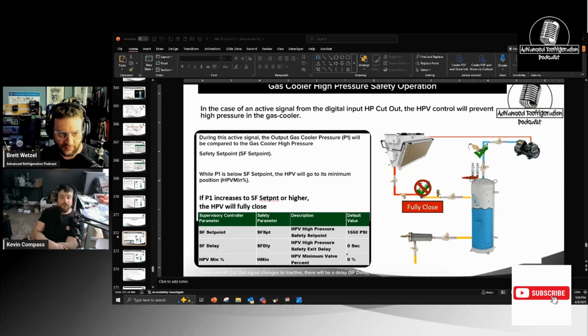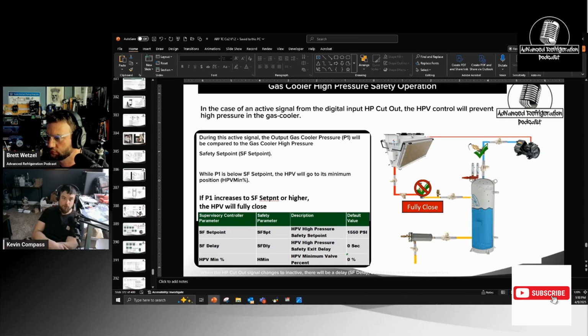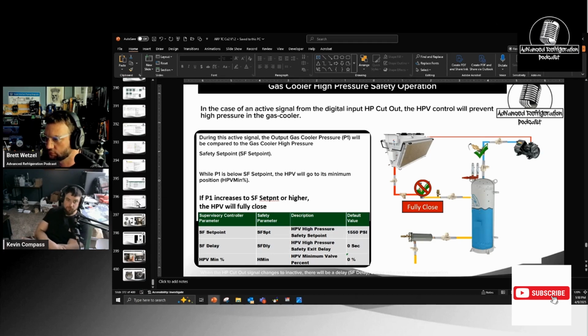That's another one. And then here's a huge issue that I see guys miss a lot on the 326As: they will have transducer issues because nobody's able to verify them, because they don't know how. On that 326A, if you hold the buttons down and read the manual, you can get to the U menus, and that will show you the actual pressure in bar, and you can compare it to whatever the EMS controller shows.